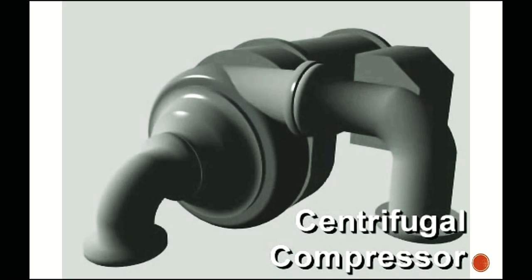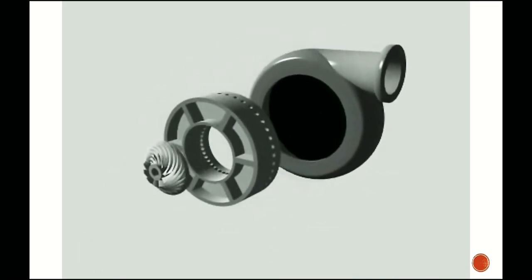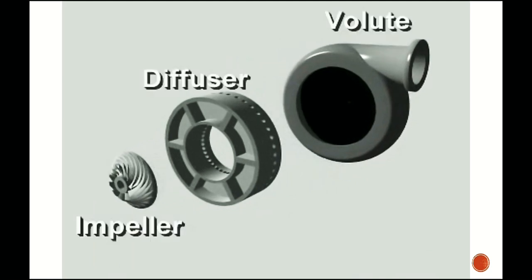The centrifugal compressor uses non-positive displacement vapor compression for compressing large amounts of refrigerant and is typically used in very large capacity cooling systems. A centrifugal compressor has three basic components: an impeller, a diffuser, and a volute casing. Large capacity centrifugal compressors may have two or more impellers or stages in the same casing.